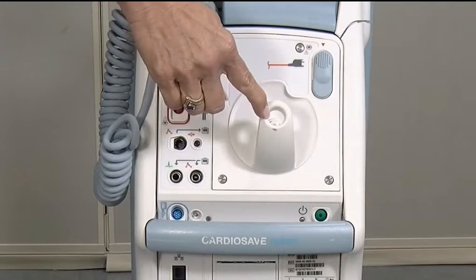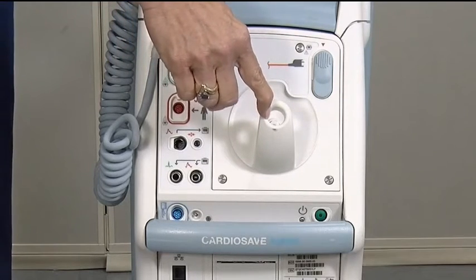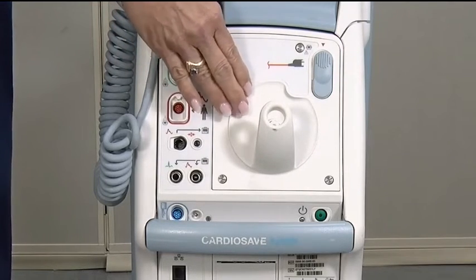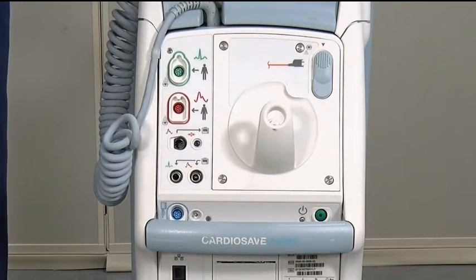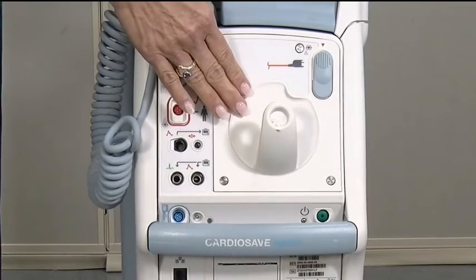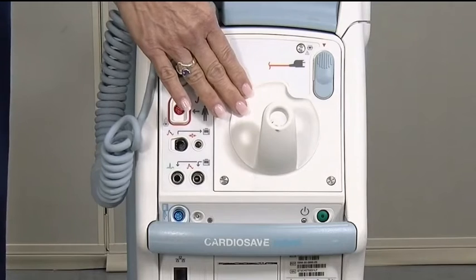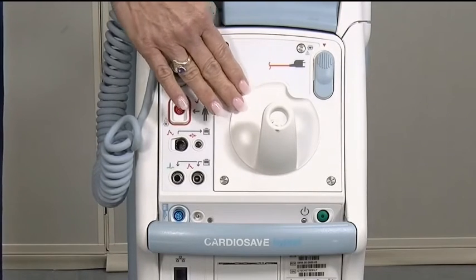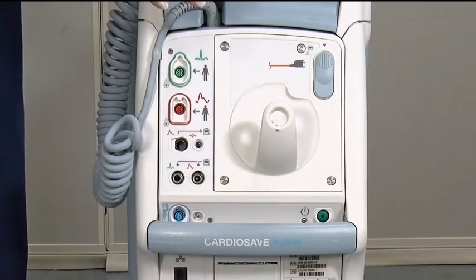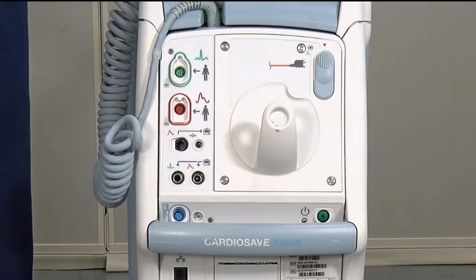Here's where you put the helium extender tubing so that you can get the helium to shuttle from the safety disc in the pump to the catheter itself. The safety disc does a couple of functions for us. One is it shuttles the helium back and forth through the catheter, and second, it also does condensation removal. So it's constantly looking at the condensation that comes into the catheter and removing it so that you never have to do anything.